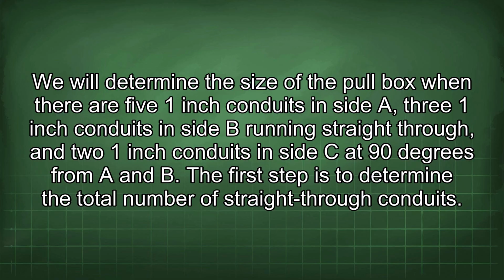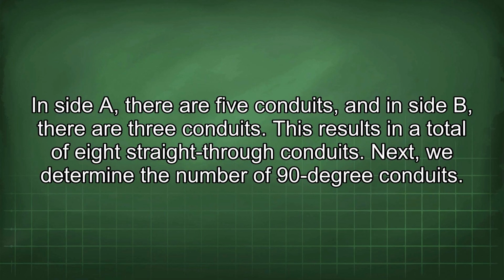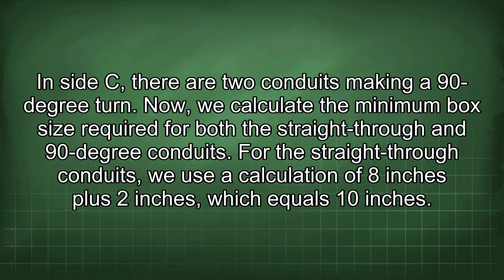The first step is to determine the total number of straight-through conduits. In side A, there are 5 conduits, and in side B, there are 3 conduits. This results in a total of 8 straight-through conduits. Next, we determine the number of 90-degree conduits. In side C, there are 2 conduits making a 90-degree turn.